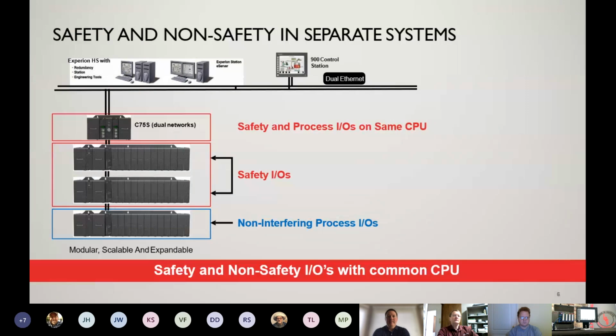The other scenario that we described is you can have both safety and non-safety CPUs on the same system. So in this application here, we have a redundant CPU network at the top, and then along the bottom here we have safety I/O and non-safety I/O, which minimizes some of the stocking that some of these plants have to do as well. If they have to carry safety spares and non-safety spares, this helps reduce some of that inventory that they have to carry.